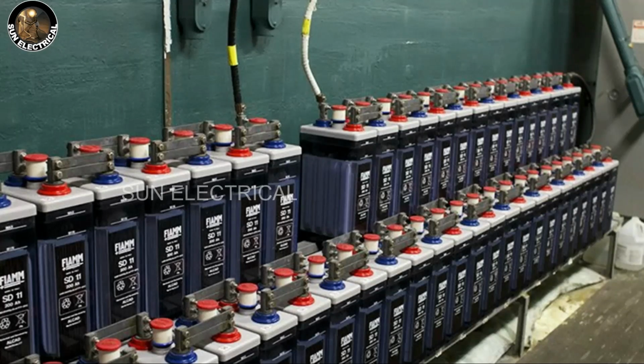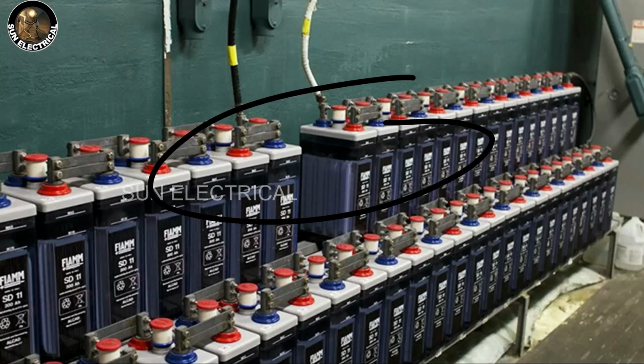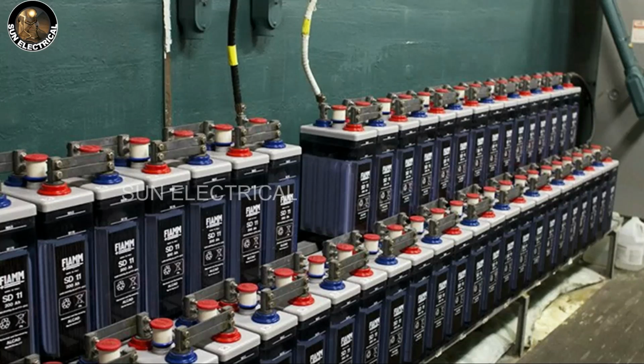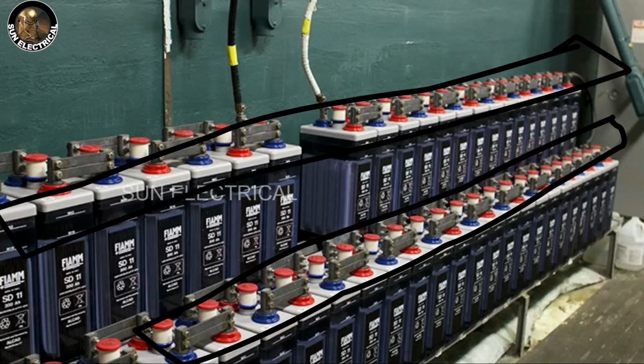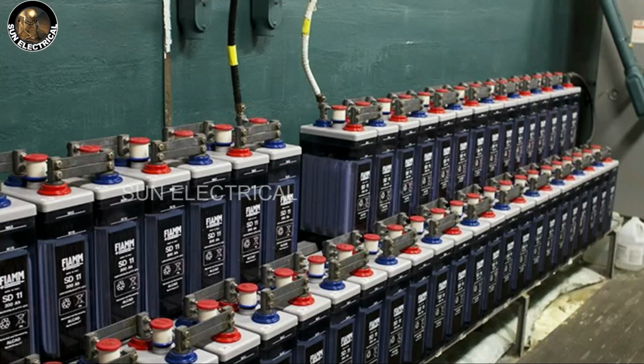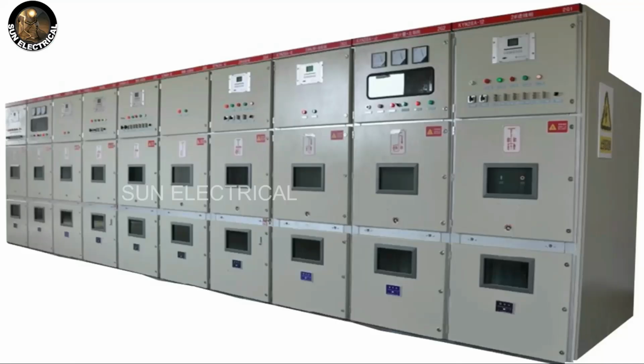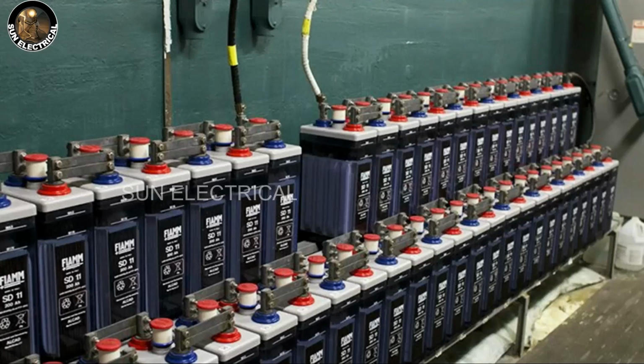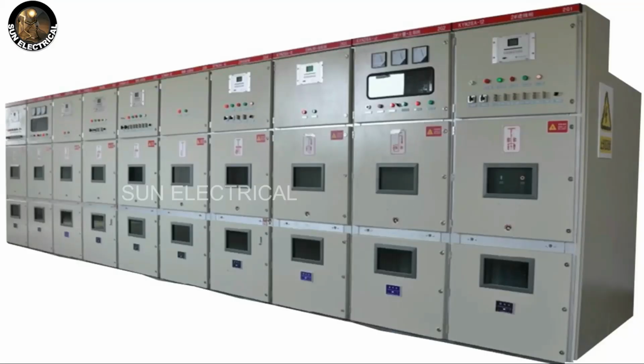Batteries are also connected in series or parallel. That means when a large number of batteries are connected, it is called a battery bank. The battery can provide only DC supply, so all control circuit devices are designed for DC supply, for example LED displays, small indicating lamps, PLCs and some other items.